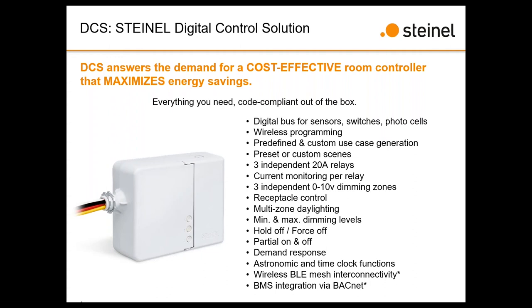Secondly, with a single device, for example, if you have a multi-zone room and you want to use this one controller to control those 3 zones, one of them might be a 277-volt circuit, the other might be a 120-volt circuit. You can independently go 120 or 277 on each of the different relays. So within one box, we can handle multiple voltages. So really strong differentiator there. It comes into play especially if I've got a 277-volt set of lighting, some accent lighting at 120 volt, and a plug load that I want to control at 120 volt. I can do all 3 of those different zones with one controller here.